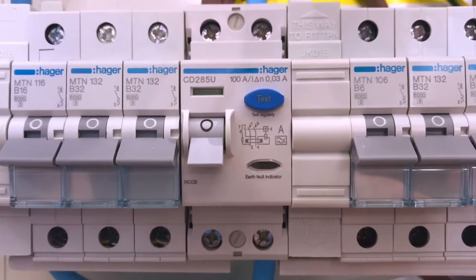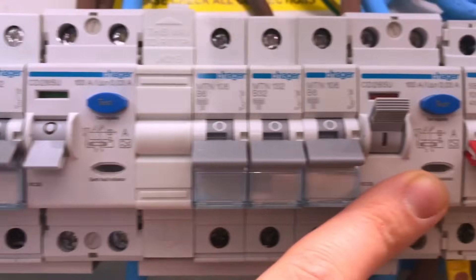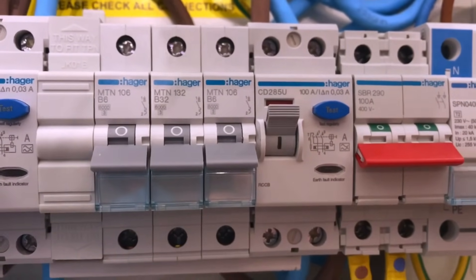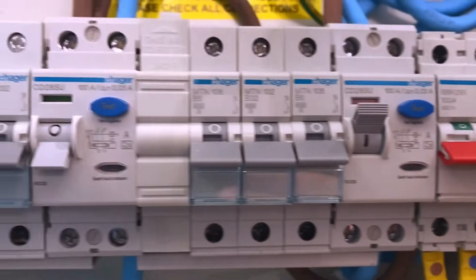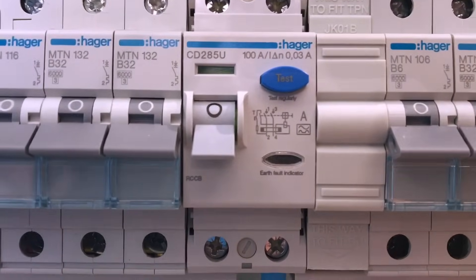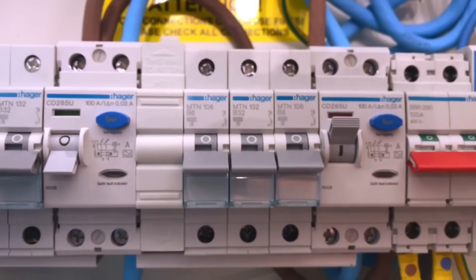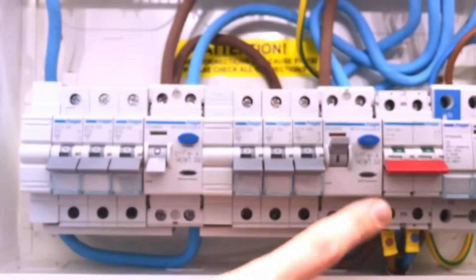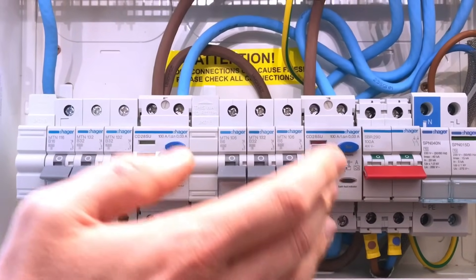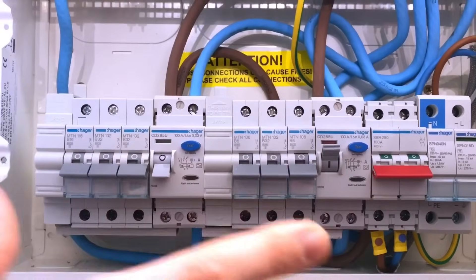Another really great thing about this consumer unit — we're calling this an 18th edition board, with surge protection built in. The RCD is now Type A, which can detect pulsating DC residual currents generated by a lot of electronic equipment in a standard house. If this weren't a Type A, there's a potential it could be almost blinded by the DC leakage current and wouldn't trip under earth fault conditions. By putting in a Type A RCD, we're overcoming that problem.